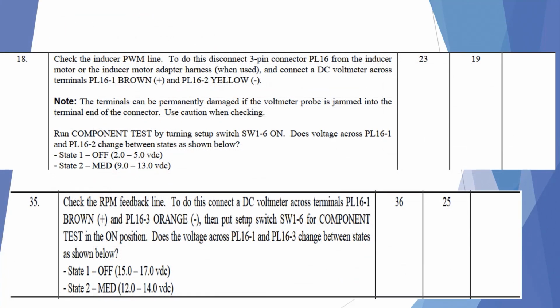Then, as with the other inducer motor, the pulse width modulation line on the ECM motor is what tells the ECM motor to run. And you need to know what voltages you need in order for the inducer motor to run. So you want to run a component test, turn the switches on to make sure that the inducer motor is going to be running. And you notice here that when the motor is off, you should see 2.0 to 5.0 DC voltage. And when it's calling for a medium speed, you should see 9 to 13 volts DC.